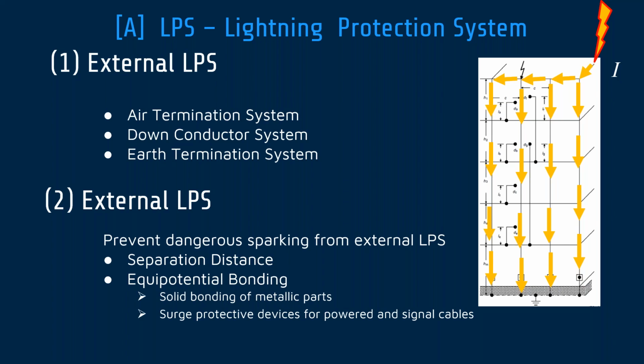Now, the beauty of surge protection devices, it's not a diode. It's not a diode, and as an electronic guy, I like the idea of a diode. Surge arresters on the medium voltage network don't clamp the voltage at that 18 kV, whatever it is. It doesn't clamp it there. At that particular voltage is when the surge arrester is fully open. Whatever energy there is, the 150, 200 microseconds of energy that is being transferred to ground, it's got to convey that current in 150 to 200 microseconds.